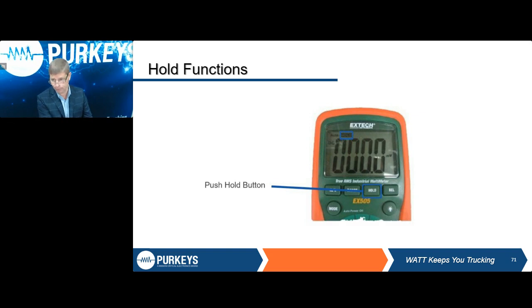Again, you're going through that service bulletin. It says, hey, I'm supposed to have this. Well, I think I read this. You can take your meter with you and compare it. Very handy if you don't have that bulletin in front of you. That sensor, like a temperature sensor, that sensor resistance is going to change based on the voltage. So you may have to look at that voltage and temperature and go back to a chart that says, hey, I checked this sensor when it was 180 degrees, so it should be here, versus that sensor at 90 degrees, the value is going to be here. So the hold function is very handy for you to have.